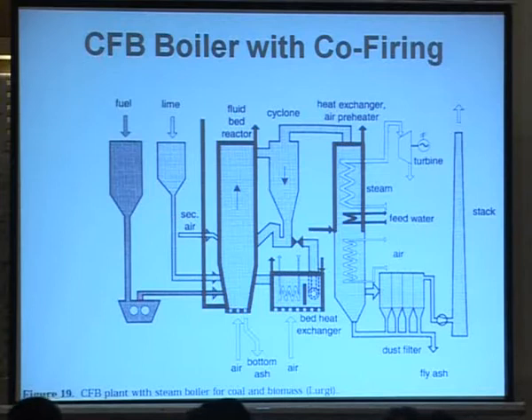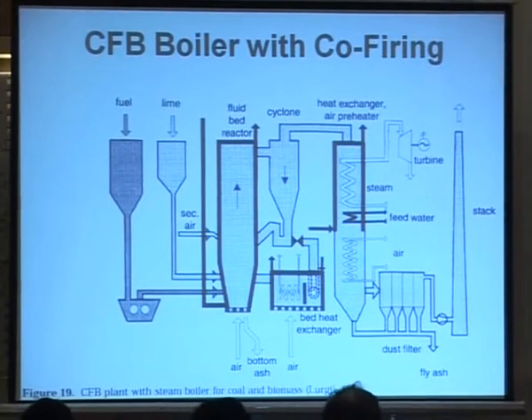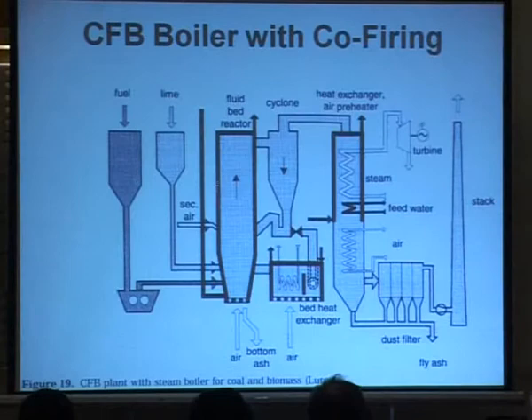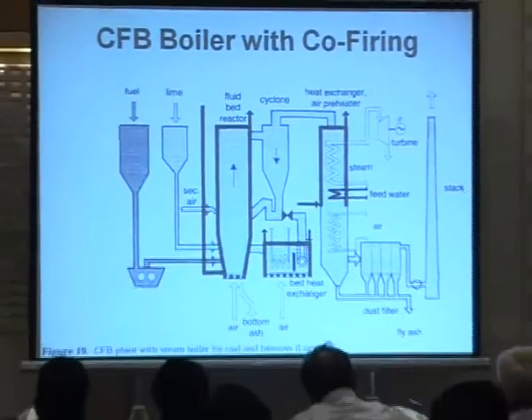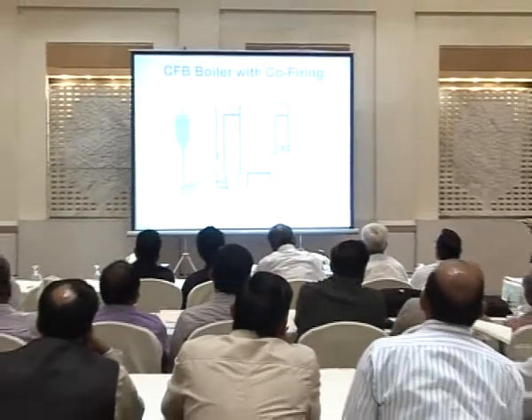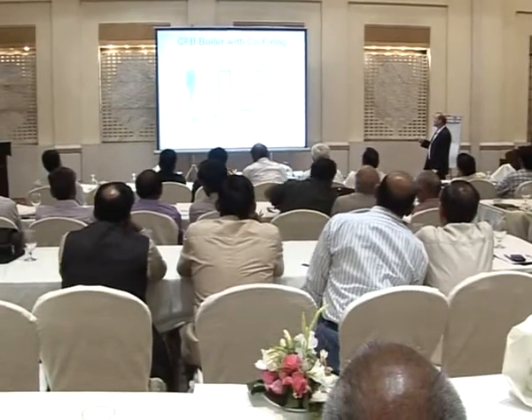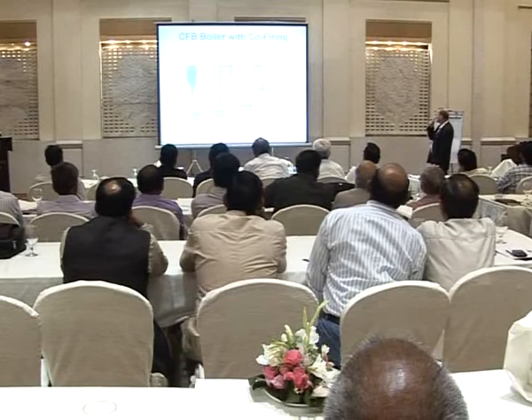This is the CFB concept for the coal and biomass, where you have different types of this setup. Here they have lime — calcium carbonate — fed into the boiler. Air is supplied from the bottom to keep the bottom ash and bed material fluidized. Ash is taken out from the bed when levels get too high. Up here you have a cyclone where you separate gas and bed materials, and then it is recycled back into the boiler. That is why it is called a circulating fluidized bed.